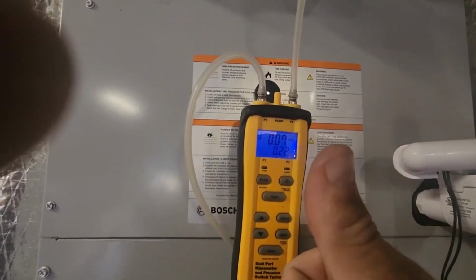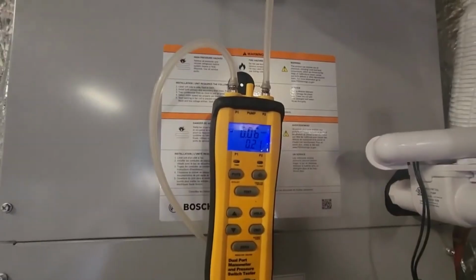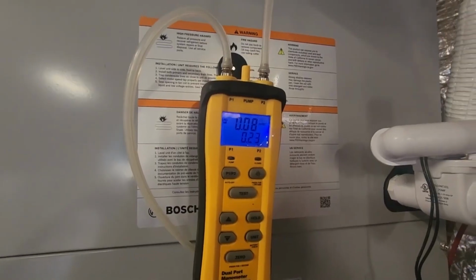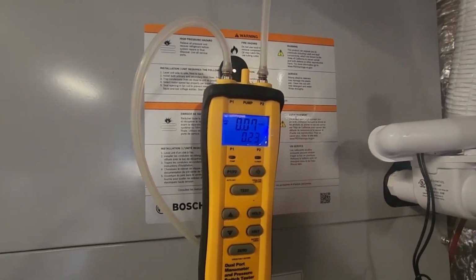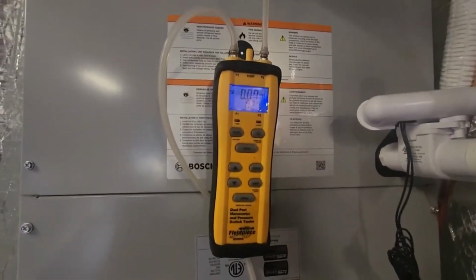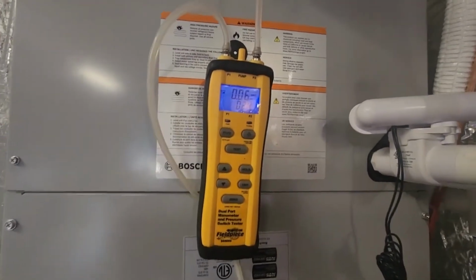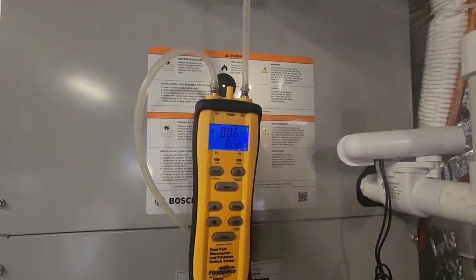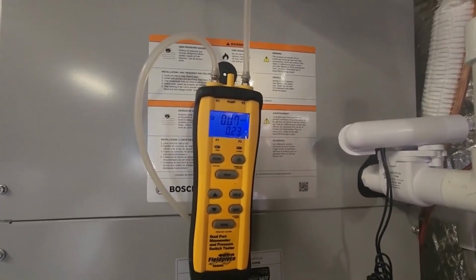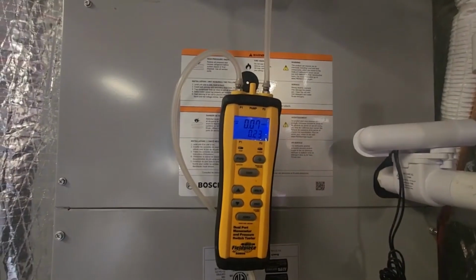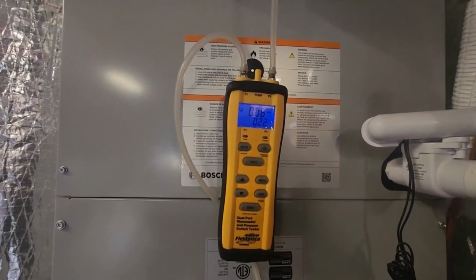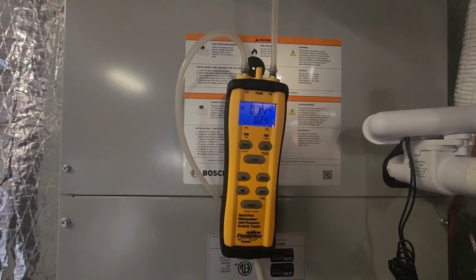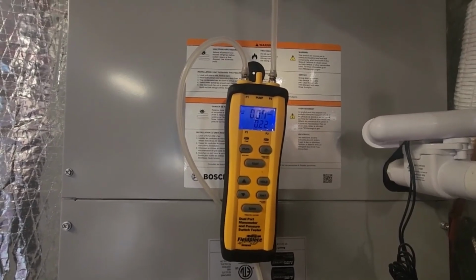I give this a thumbs up. Let's do second stage. Let's open them both up and see what our static is without the filter in, and that'll conclude this static pressure test, which is awesome. All manufacturers put what their recommended maximum static is. On these, it's 0.8, I believe. We strive for 0.5, but man, this thing's getting awesome airflow, and it's going to last me a long time.